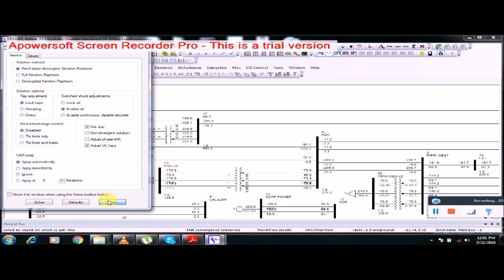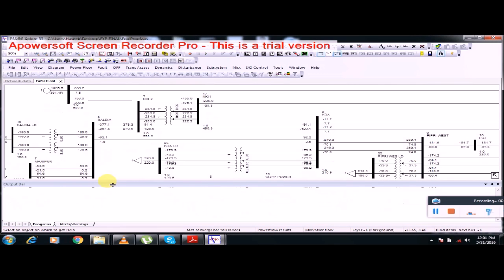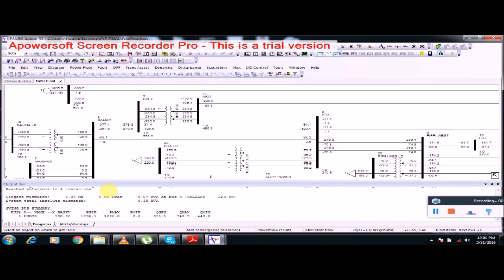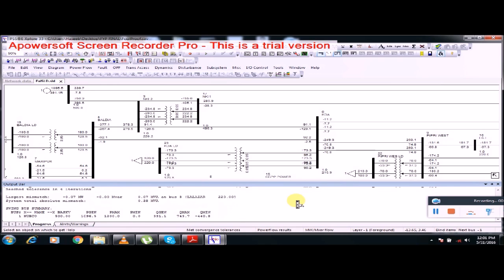The load flow is performed using the fast-decoupled Newton-Raphson method. The process converges in four iterations, with the largest mismatch of 0.07. The swing bus is Hubco, which is generating 1096 megawatts of power.